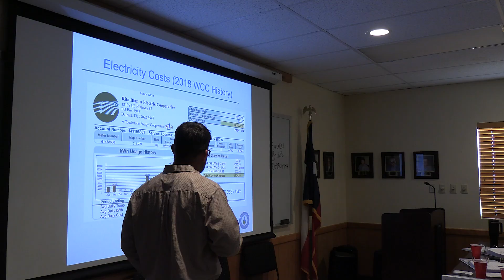The electrical generation is what we're going to compare back to that. So remember that first gen set we put on, we evaluated it by testing natural gas, took voltmeters out to measure the volts and amps, measured the power factor on each of the runs, and added it up to see if he could generate with the current delivery of natural gas for anywhere in the ballpark of what he could buy power for.